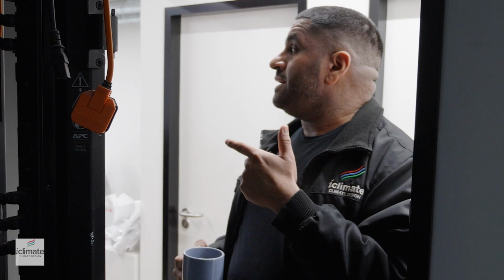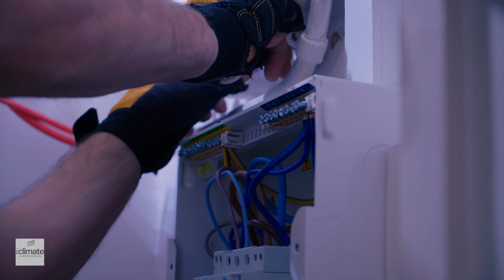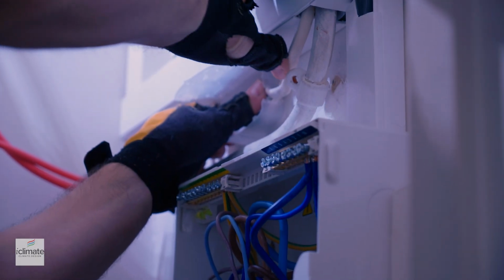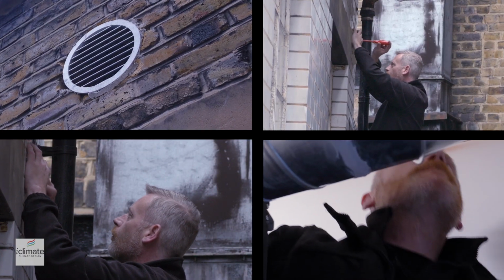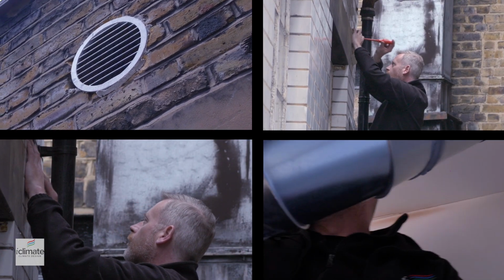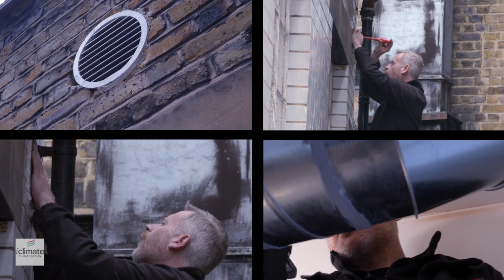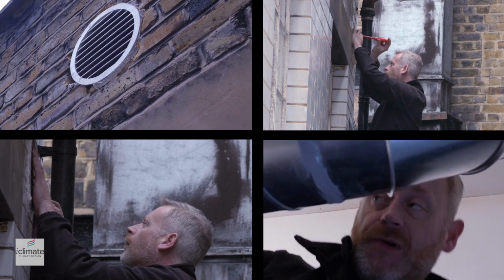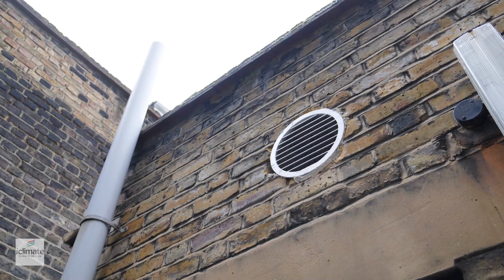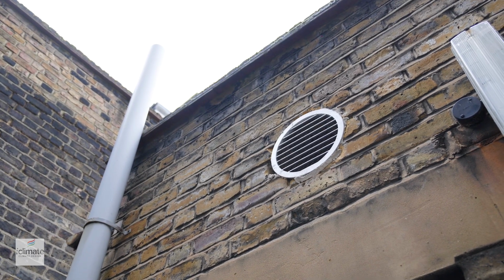The fuse board here on this job is actually a plastic old fuse board, so we replaced it with a garage style metal clad fuse board with a dedicated supply running an FP200 fire rated cable. There are two large penetrations that need to be done within the building fabric, and these are typically 150mm to 200mm or slightly even larger. When they get larger, we get structural engineers involved to come to site to assess the load and where we can penetrate and how we can penetrate to make sure that we're all compliant. But here we did a 200mm spigot.